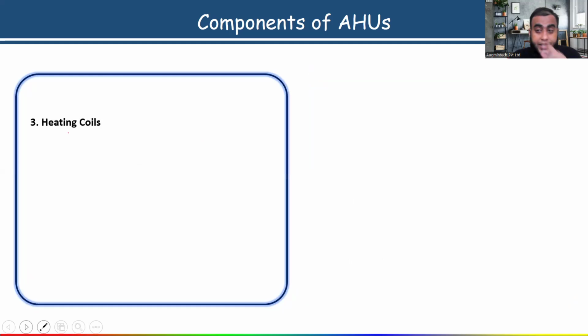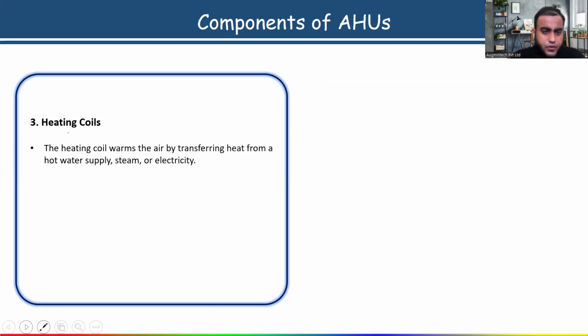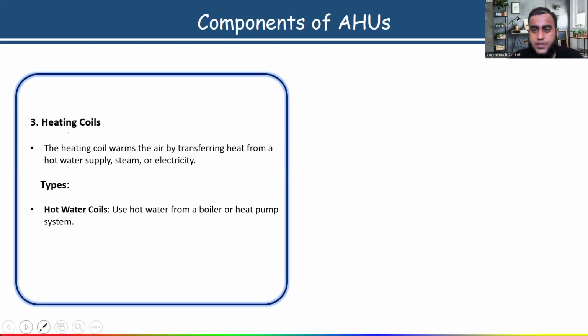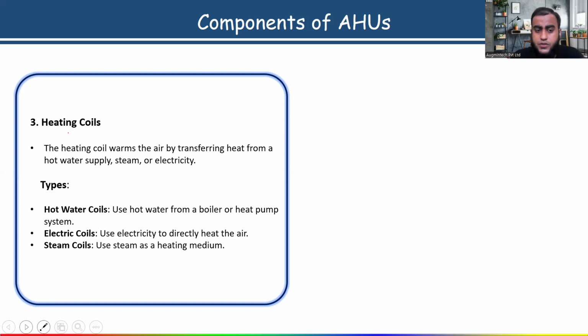Next thing, heating coil. All of you know the heating coil warms the air by transferring heat from a hot water supply, steam, or electricity. Is it clear? Different types of heating coils are there, like the hot water coil, which uses hot water from a boiler or heat pump system. Then we have an electric coil, which uses electricity to directly heat the air. The steam coil is also there, which uses steam as a heating medium.